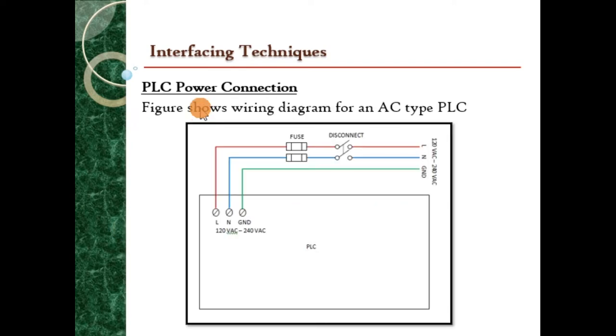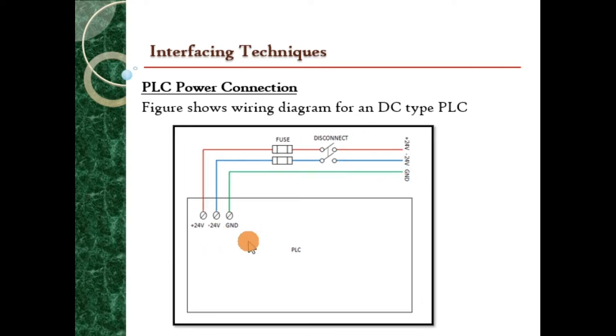This power connection shows the wiring diagram for an AC type PLC. You have an AC input, and this AC input must be correctly connected to the AC type of PLC. The AC type of PLC ranges from 120 volt AC to 240 volt AC. While this figure shows the wiring diagram for the DC type of PLC, the inputs to the DC type are 24 volt plus and minus, and you also have a common ground here. So we have to make sure that the connection is correct.